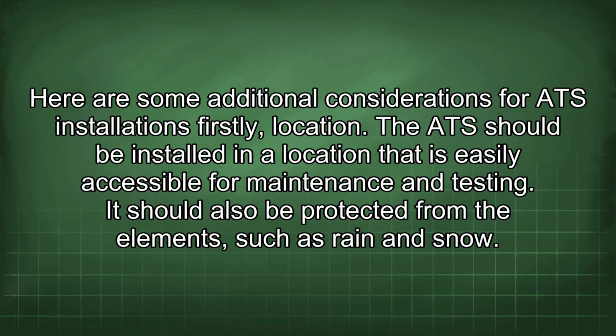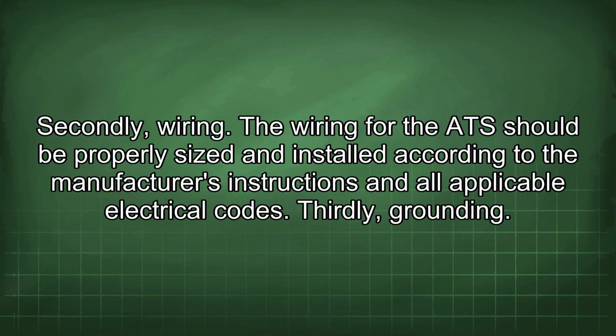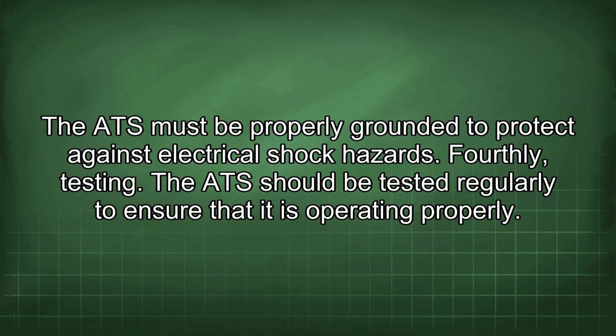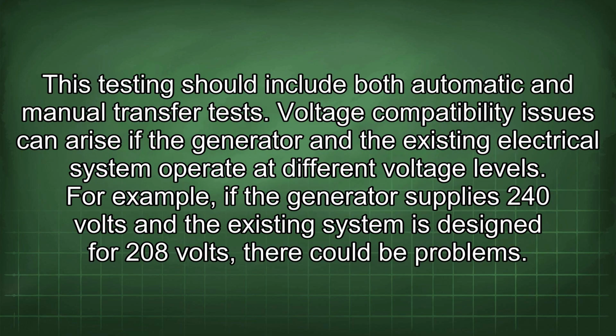Here are some additional considerations for ATS installations. Firstly, location. The ATS should be installed in a location that is easily accessible for maintenance and testing. It should also be protected from the elements such as rain and snow. Secondly, wiring. The wiring for the ATS should be properly sized and installed according to the manufacturer's instructions and all applicable electrical codes. Thirdly, grounding. The ATS must be properly grounded to protect against electrical shock hazards. Fourthly, testing. The ATS should be tested regularly to ensure that it is operating properly. This testing should include both automatic and manual transfer tests.